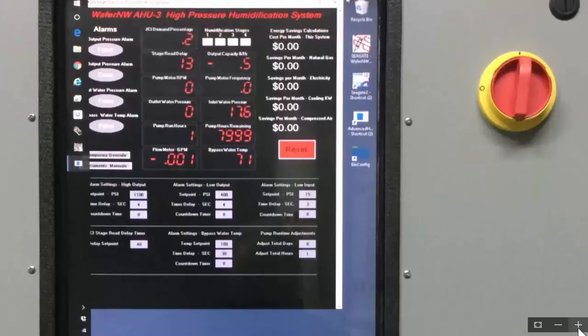So I talked about on the output side, the discharge high pressure side, there's two alarms. This top one here is the high output pressure alarm, and that one's set at around 1100 or 1200 psi. And I can see right here, here is the alarm set point. It's actually at 1100 psi. This is the low output pressure alarm. So there's a high output pressure alarm and a low output pressure alarm, and that's this one here, alarm setting, low output, 400 psi.